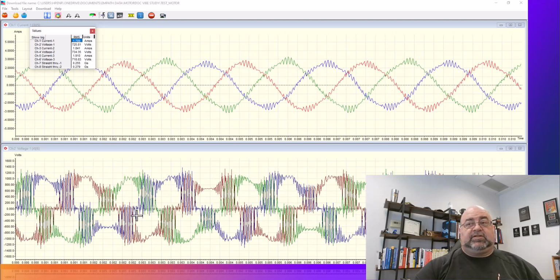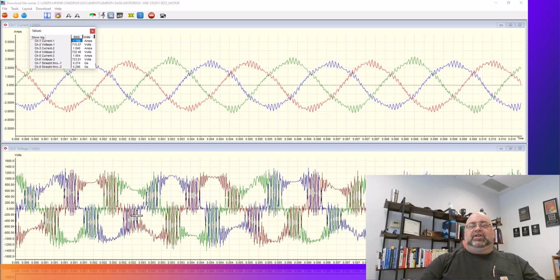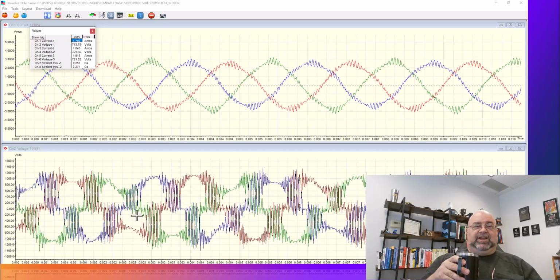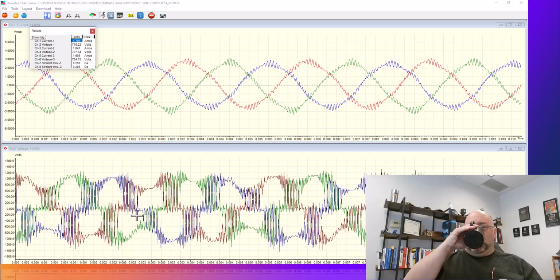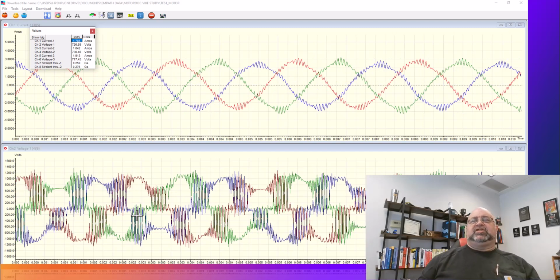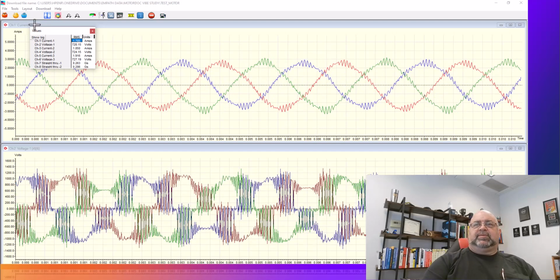Now this machine is deliberately set up incorrectly. So the drive parameters aren't exactly right. You can see that it's really dirty. It's connected directly to the motor. It is set for about 50 hertz. Now, what are some of the things I can do?